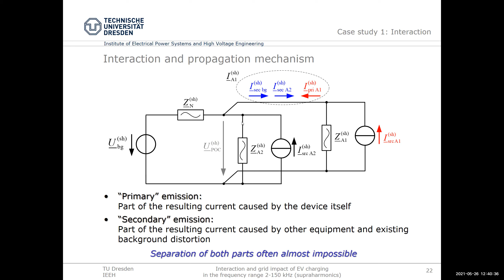What is also important, if you measure the current of that particular EV, is that it's composed, strictly speaking, of a part caused by the EV itself, called the primary emission, and a part coming from the other EV, called the secondary emission. There can even be a secondary emission from the background if there's already voltage emission available from the network side, which makes it virtually impossible to decompose them. You could switch off one of the cars to see what the emission of that one car is, but the problem is that switching another car on or off also changes the impedance situation, making it even more difficult, because then the current of one device will change again.